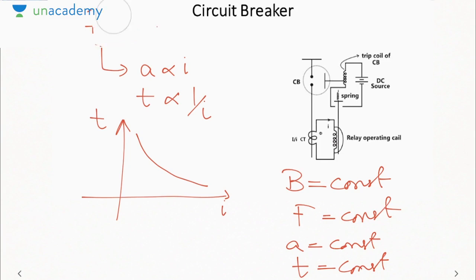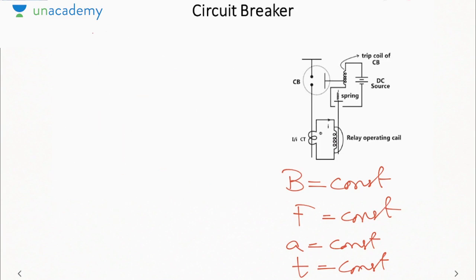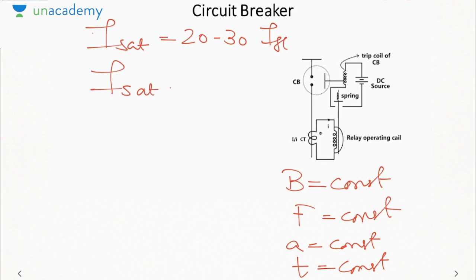That is why in your protective current transformer, the saturation current is usually 20 to 30 times full load current. Whereas in a measurement type of transformer or instrument transformer, saturation does not occur. Why? Because you will never exceed the rated current. Even if you exceed, how much will you go? 2 times, 3 times, but not 20 to 30 times. Hence their saturation current is 2 to 3 times full load current. Because in a measurement system, there will not be abnormal conditions, hence your saturation current is less. So the protective current transformer has a higher saturation current, whereas your instrument current transformer has a lower saturation current.